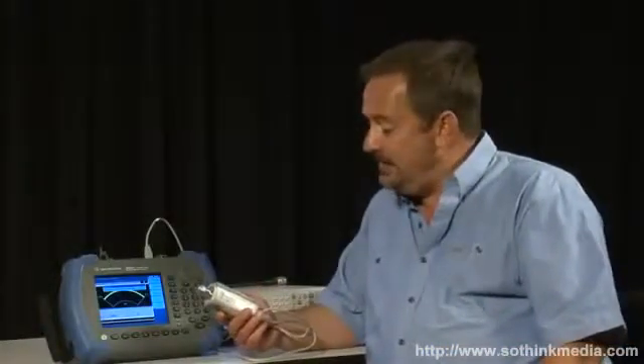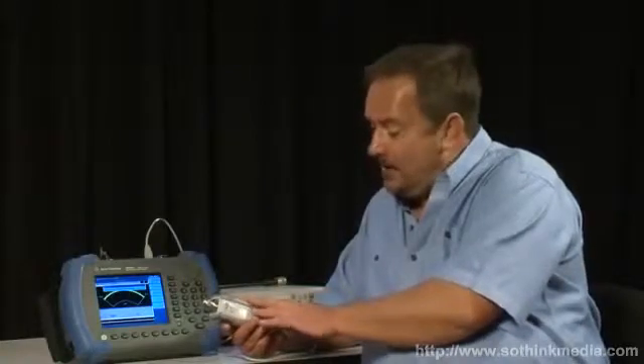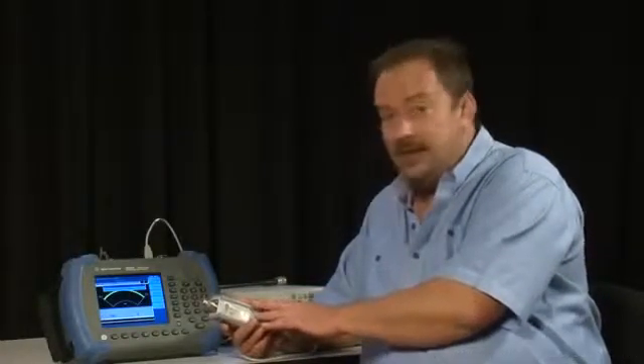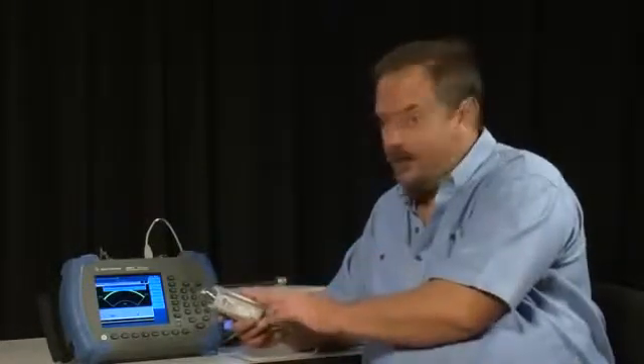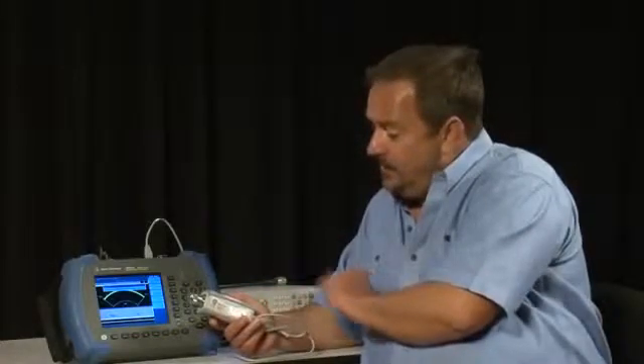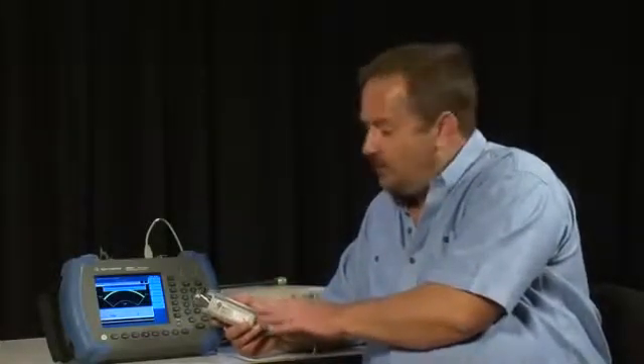It's a good time to point out that unlike a normal power sensor meter where you have to manually enter the calibration factors for that particular sensor into the meter to get an accurate measurement, with the U2000 series the power factors are automatically loaded in. They're stored in memory inside the unit. Plus, you don't have to zero or calibrate the sensor—it's auto-zeroing and auto-calibrating.